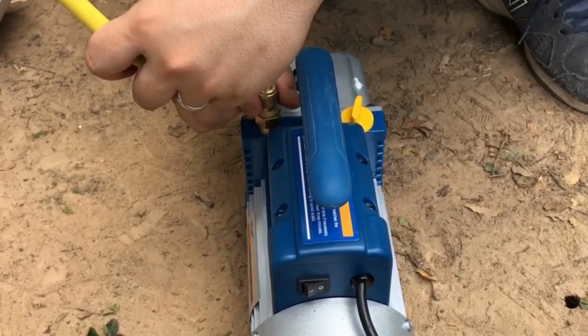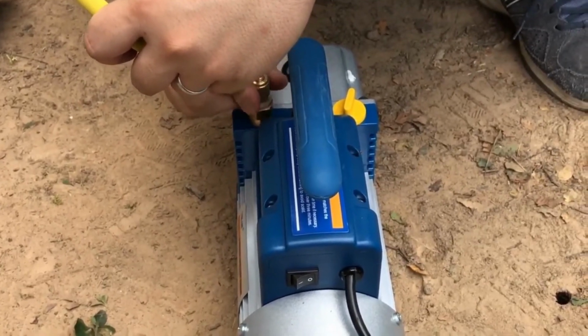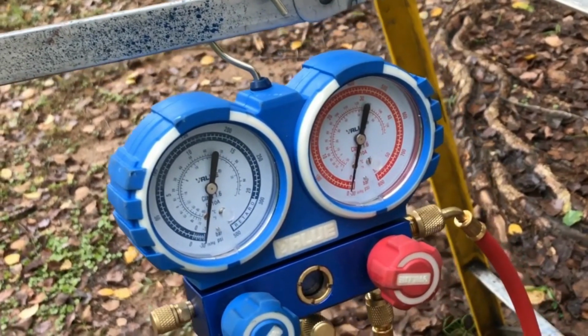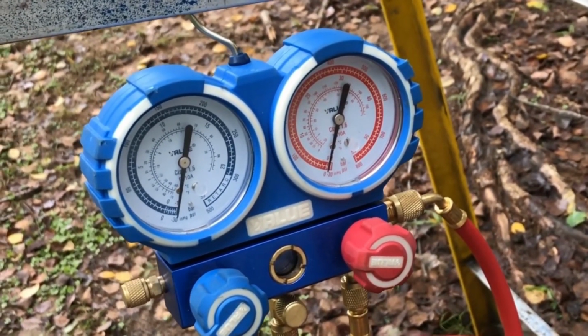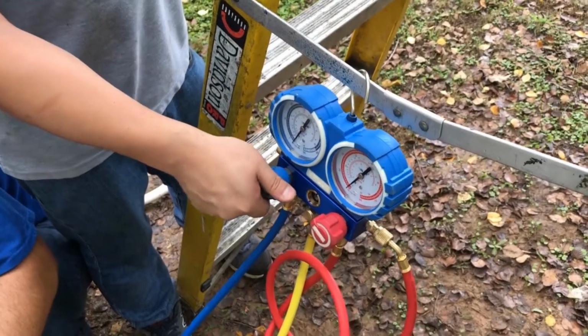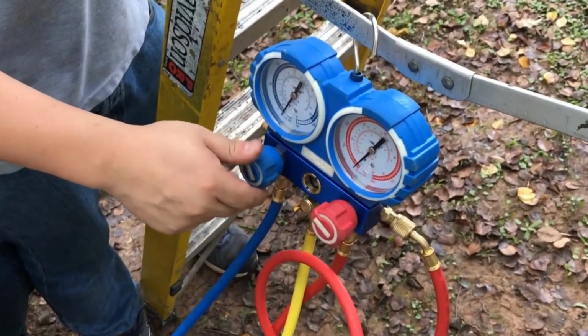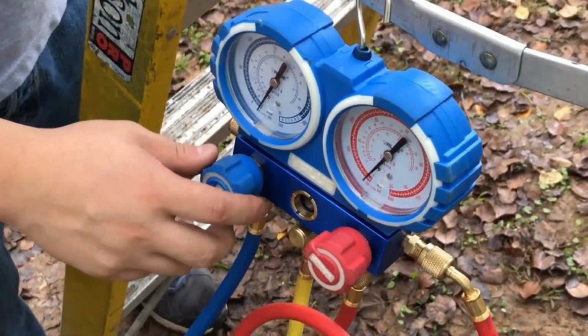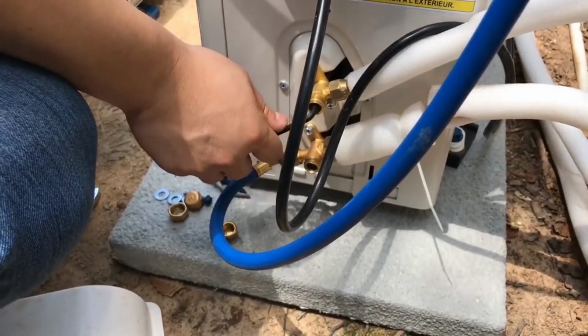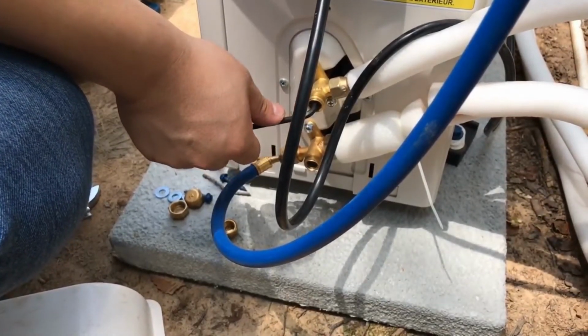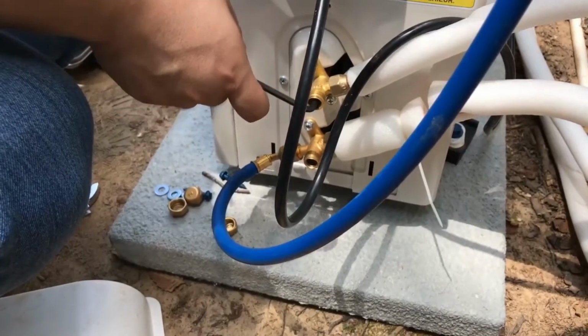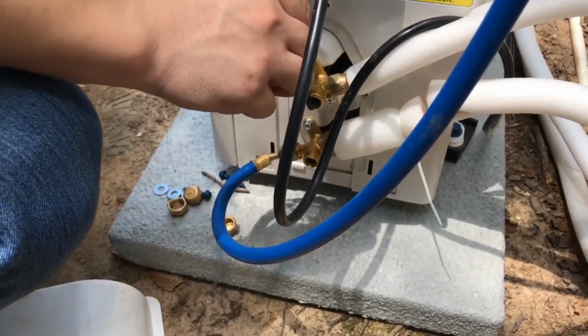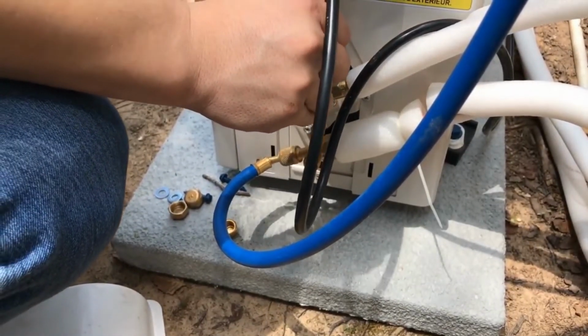Next, the technician will use a vacuum pump and gauges to remove all air and moisture prior to releasing refrigerant into the lines. After the vacuum is complete, close the manifold gauge valve. Use an adjustable wrench to remove the service valve caps and use an Allen wrench or hex key to fully open both service valves, releasing refrigerant into the system.